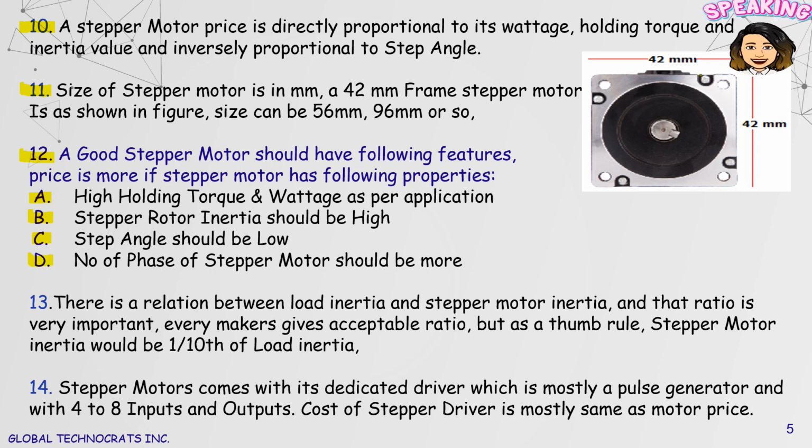There is a relation between load inertia and stepper motor inertia, and that ratio is very important. Every maker gives an acceptable ratio, but as a thumb rule, stepper motor inertia should be 1 by 10th of load inertia. Stepper motors come with a dedicated driver, which is mostly a pulse generator, with 4 to 8 inputs or outputs. Cost of the stepper driver is mostly the same as the motor price.